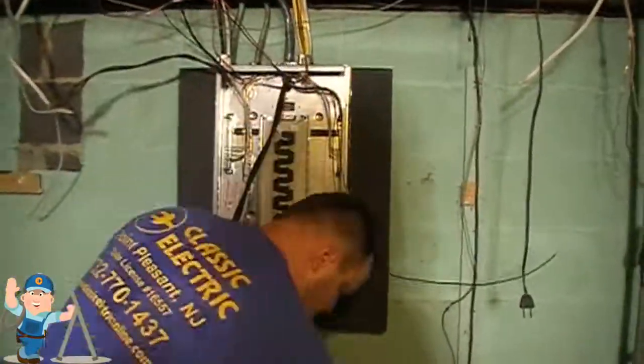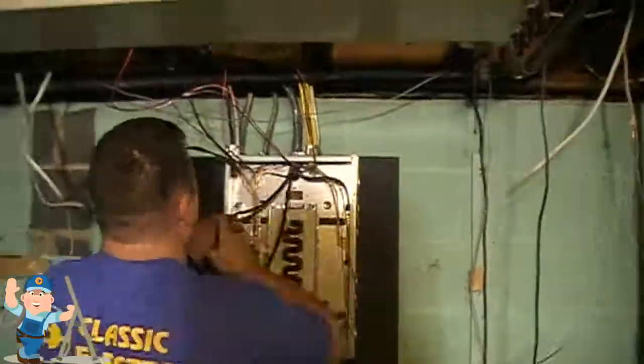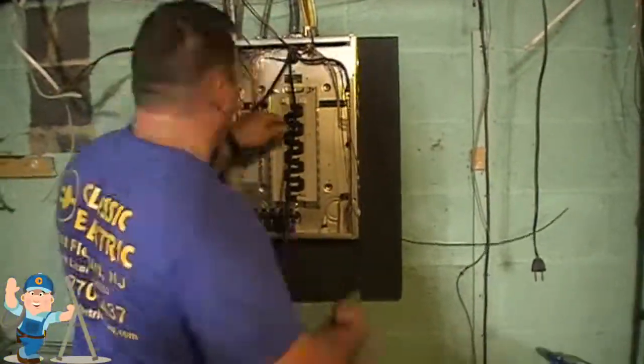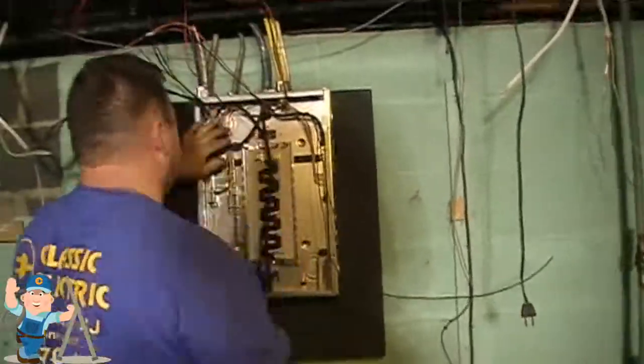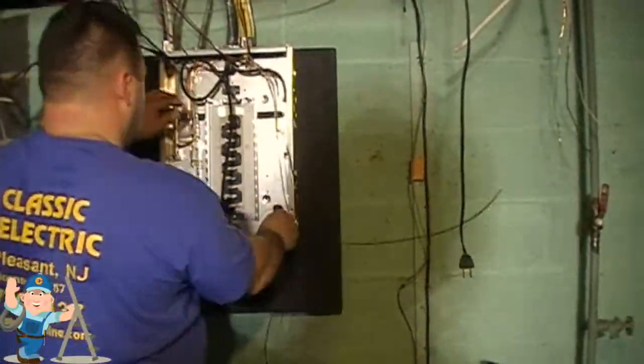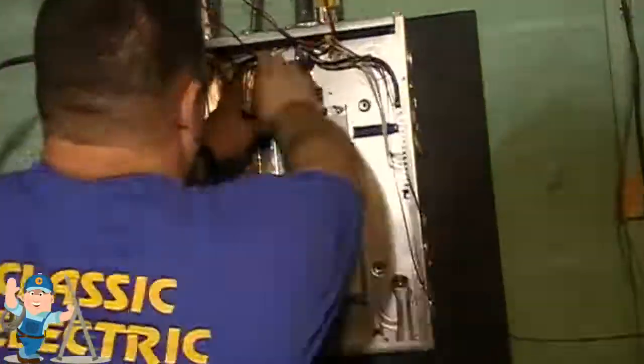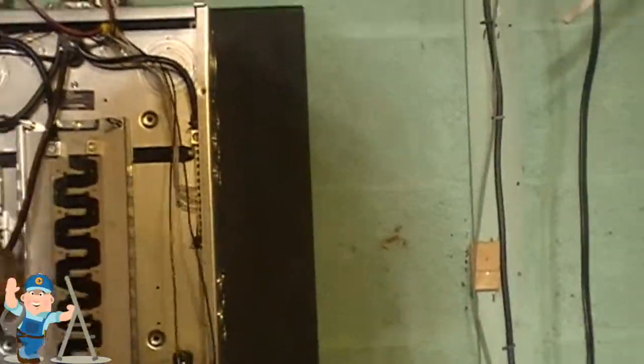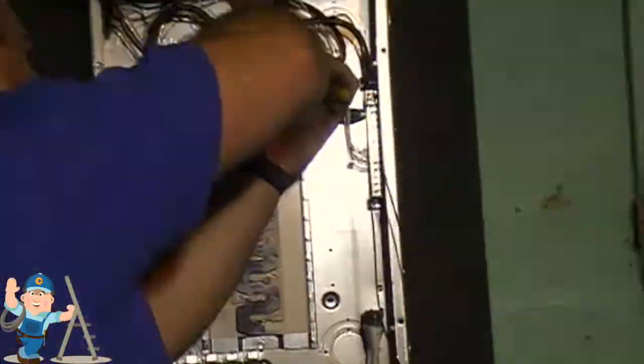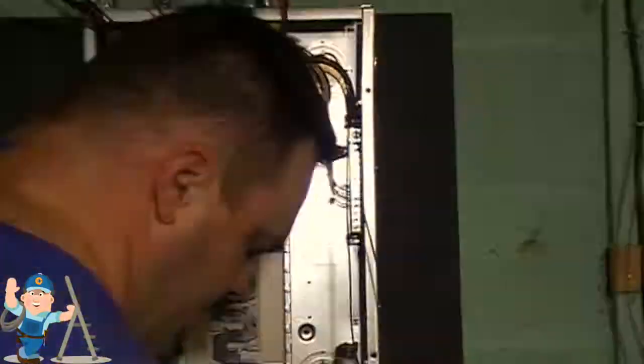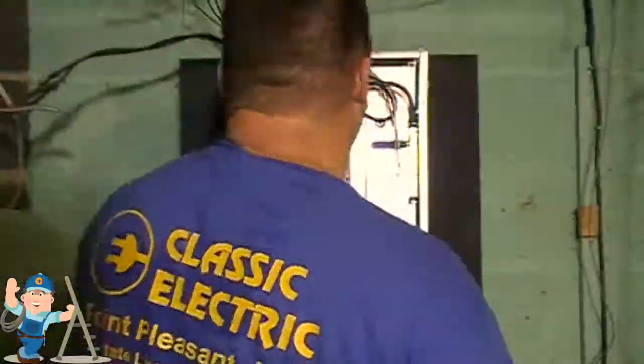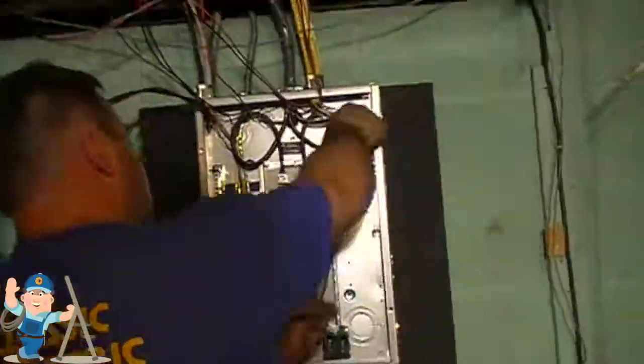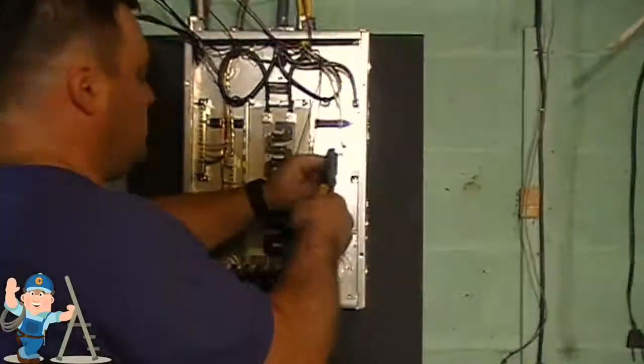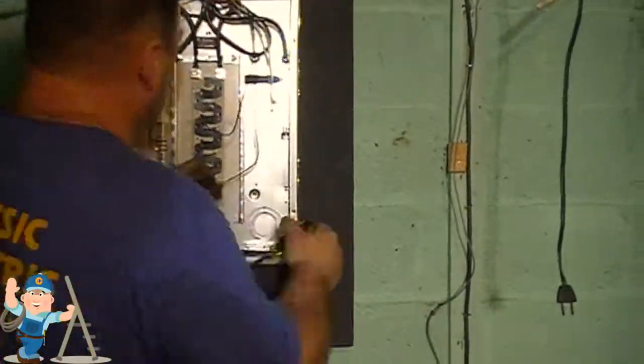In this sub panel, you always want to isolate your grounded neutrals from your equipment grounds so you don't have any objectionable current flowing on grounded parts in the house, such as copper water pipes or galvanized pipe, or anything that can conduct electricity. Those are all grounded, and if current flows on them, it could be a fatality if someone got in the middle of that circuit and completed a path to ground. So it's very important to isolate your grounds and neutrals here at the sub panel.